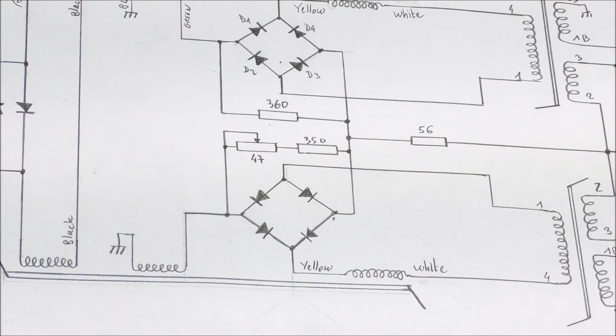The goal is to have a DC current in this winding, for example, when the AC voltage here is in phase with the reference phase of the motor, or in opposite phase. There should be a DC current in that winding, much higher than in the other, in order to create an imbalance. This provides the saturation of this transformer or the other. So at a given time, only one transformer is saturated, and when the motor stops, neither transformer is saturated.